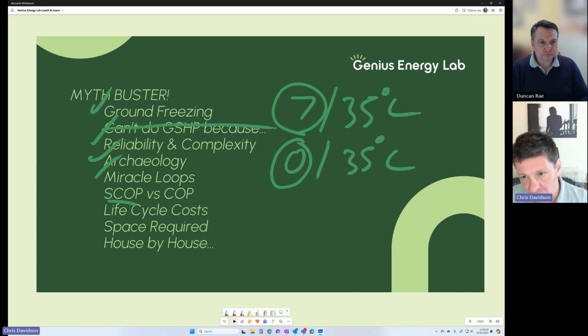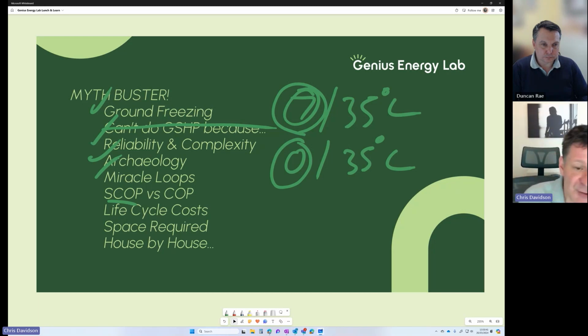For air source, a bit more complicated. You've got to look at regional air temperatures to get the variability in the source temperature, but you've also got to look at humidity. In the UK climate, which is never that cold, so the air doesn't dry up, it's always this damp and cold that we get during the winter, you'll get condensation forming on the coils of air source, and therefore that will freeze because the coils are cold, and you need to defrost. So you've got to consider not just the temperature, but the humidity of the air, and that's something that ground source just doesn't suffer from. So please don't use COP, use seasonal COP.